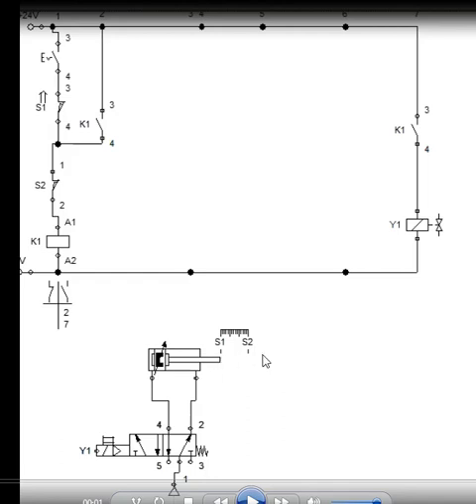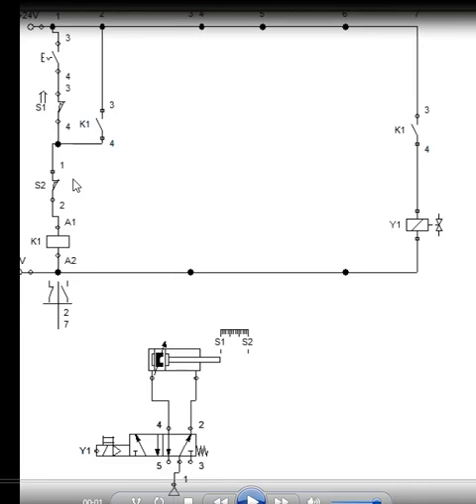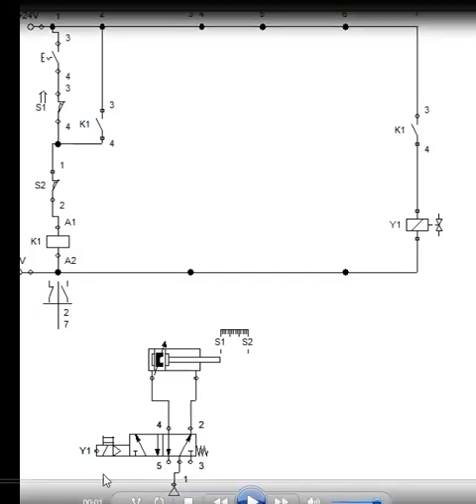As soon as it is reaching S2, what is happening is the normally closed contact is open. This piston is opening this normally closed contact and the current which was supplied to this K1 coil because of the latching, there I have provided a latching, so because of the latching the current was going, that also will not go to your K1 coil and your Y1 will not get the current. Therefore, this Y1 will not get the current, it will be de-energized.